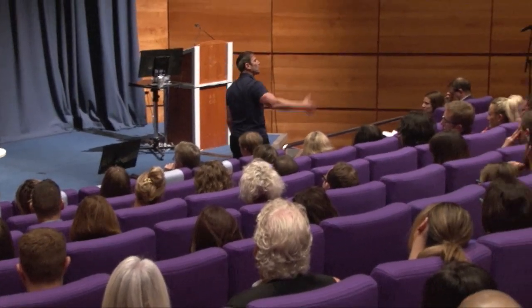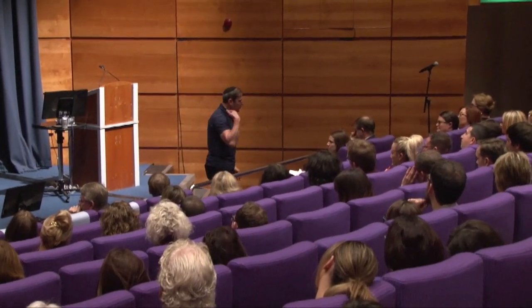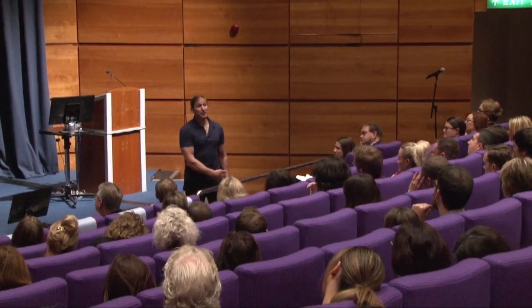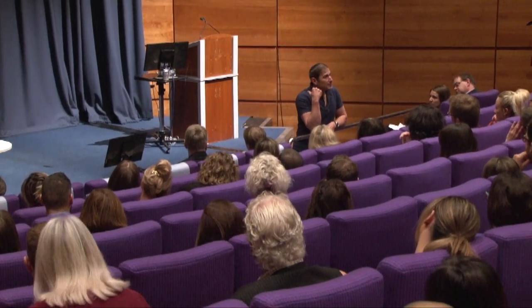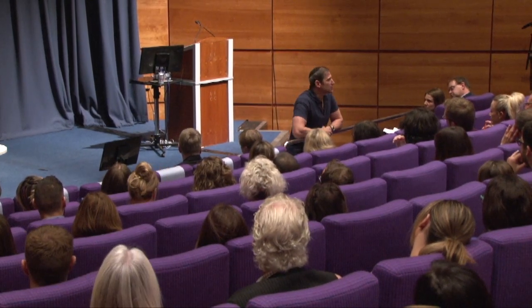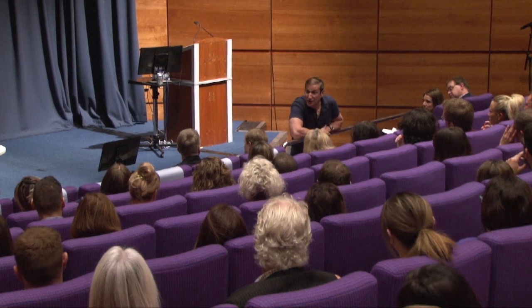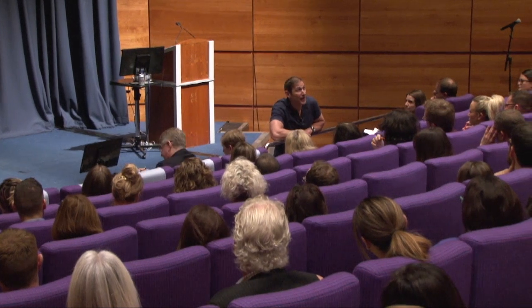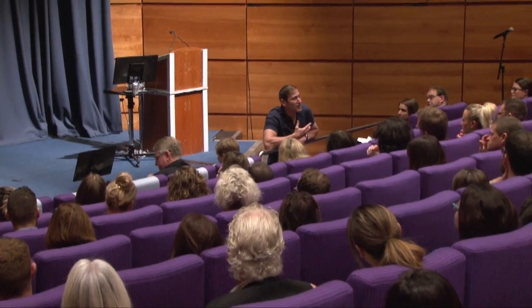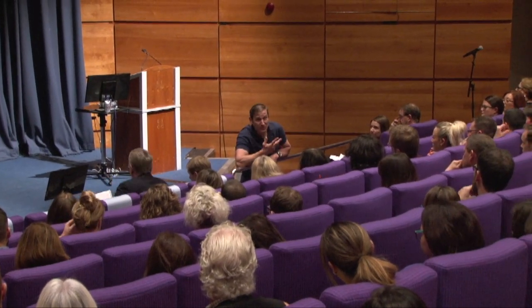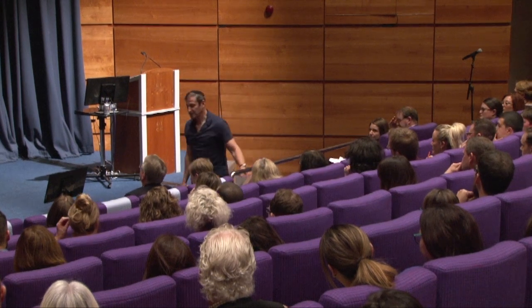What radio frequency exposure levels for B1 would you tolerate before you want this app to tell you, hey, you're irradiating this thing? If it's in the ankle and it's going to be exposed to less than 1% of the energy going on in this guy's pituitary, maybe you don't want to be warned about it. Maybe you'll say, I'm only going to care about this thing if it's going to be exposed to 5% of the energy going on inside the center, like mom standing at the front of the machine. How about that? Do you understand what I'm saying? You can accept predefined, because that's how this was labeled, or you can change them, or you can define your own for any device you want to create.